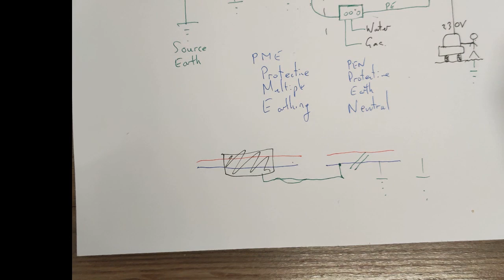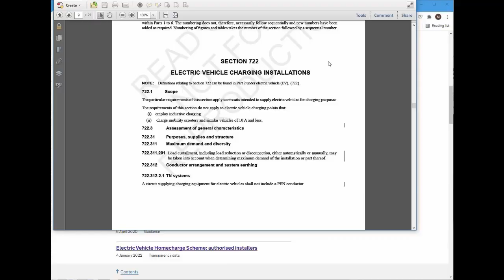So in the original BS 7671, there are only a couple of methods that you could detect an open PEN fault. Things have moved on since then, which is why there's now Amendment 1, and we'll just have a look at that now. So here we are, this is Amendment 1 of Section 722 relating to electric vehicle charging. The bit that's really changed is this bit here, relating to how vehicle charging units protect against open PEN faults. And as you can see here, a PME earthing facility shall not be used as the means of earthing for protective conductor contact of a charging point located outdoors, or that might reasonably be expected to be used to charge a vehicle located outdoors unless one of the following methods is used.